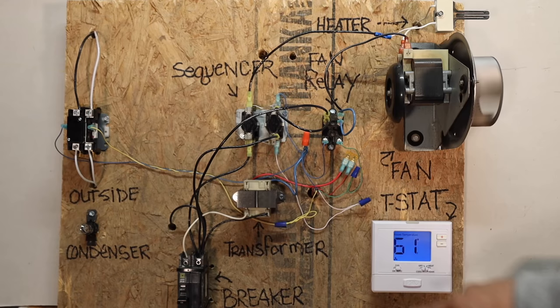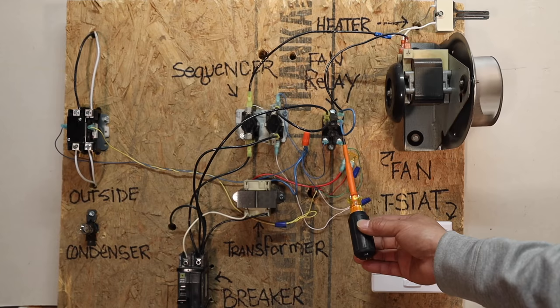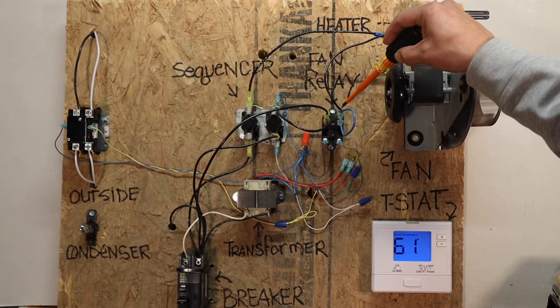When you turn it off, the 24 volts de-energizes from here, this bimetal pulls back down and breaks the circuit up here, and then it stops power from the blower motor.